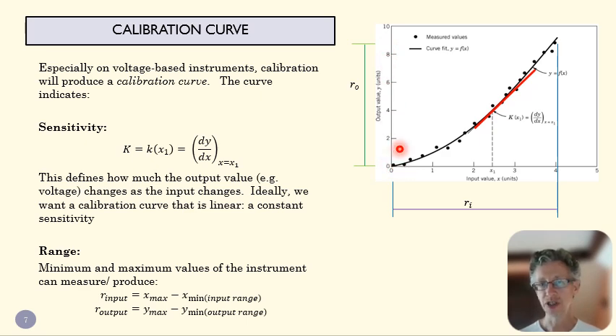Likewise, we can talk about its output range. This is going to output from zero volts to about nine volts. And let's say that's the limit here. It might be that I might do what's called saturate. If I put a 10 newton load on this, it might still give me a reading of nine volts. And that's what we call saturation. If we've applied so much of the quantity, or if the quantity is outside of that range, it's going to give us just a flat zero, or it's going to give us the maximum voltage, whether we change it or not. And so we want to make sure that our instrument isn't saturated, that we're using it within its intended range, both in terms of the input and the output. And that's our quick little introduction to measurement basics.